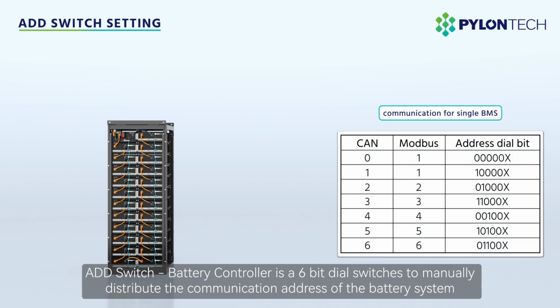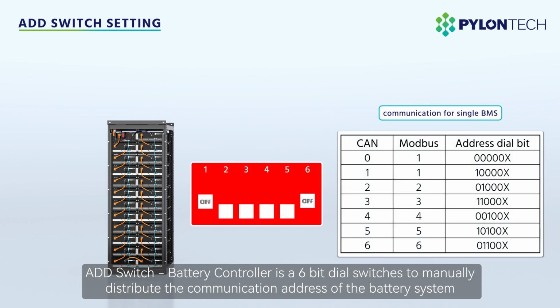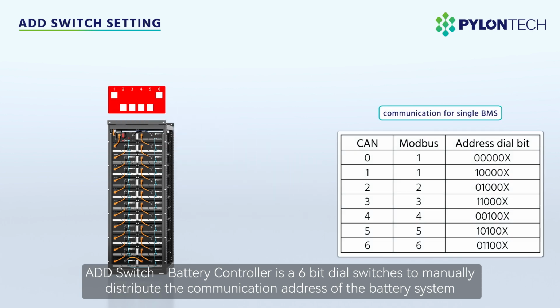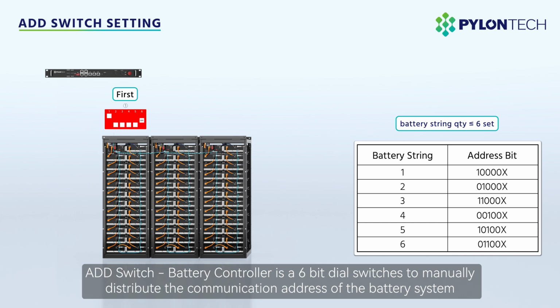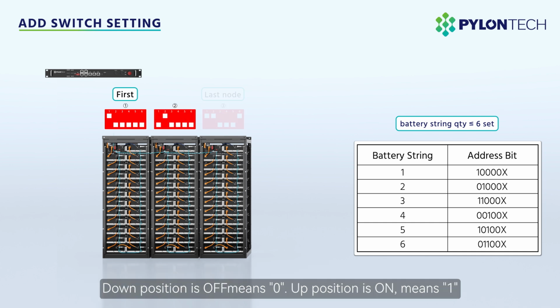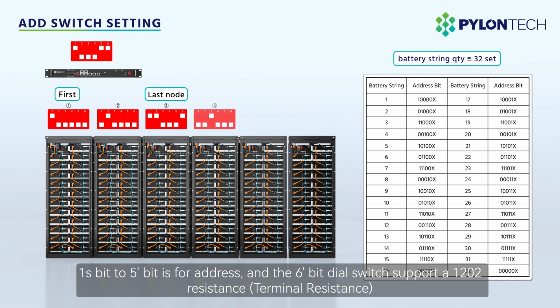DIP switch. Battery controller has a 6-bit dial switch to manually distribute communication address of the battery system. Down position is off, means 0. Up position is on, means 1. 1st bit to 5th bit is for address, and the 6th bit dial switch supports a 120 ohm resistance.